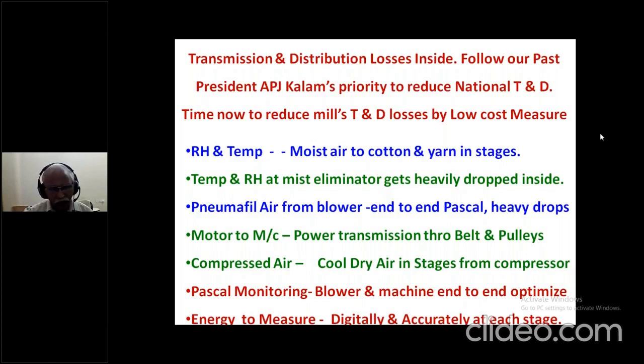Leave alone the compressed air monitoring, we have to maintain Pascal monitoring from the blower to the machine also, especially on the carding waste collection. We are maintaining almost 1500 pascals at the blower end, and we are only receiving around 500 to 600 pascals at the carding end. Almost 1000 pascals is getting dropped. This also is a point of T&D loss. It can definitely be controlled.